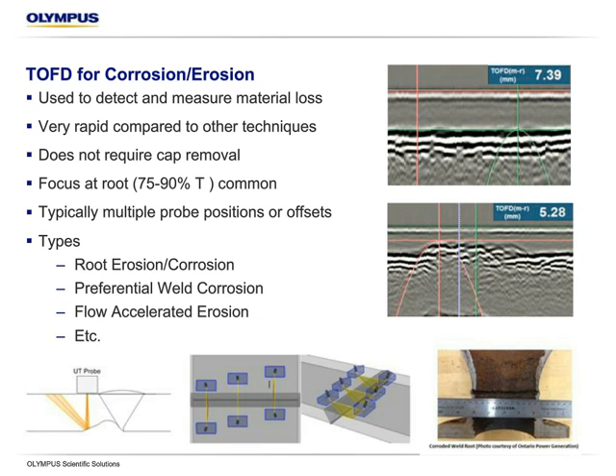Typically when we do this, to get proper, very precise remaining wall type measurements, we're going to do a scan at maybe 3 different index positions. It's kind of shown there in the bottom. This is going to increase our accuracy in the actual remaining wall thickness. So we'll do one centered around the weld, and then one offset one way, and then offset the other. This can be done all collectively if the unit can handle that many channels and you have the right scanner, or it can be done in 3 separate acquisitions and the data compared that way.